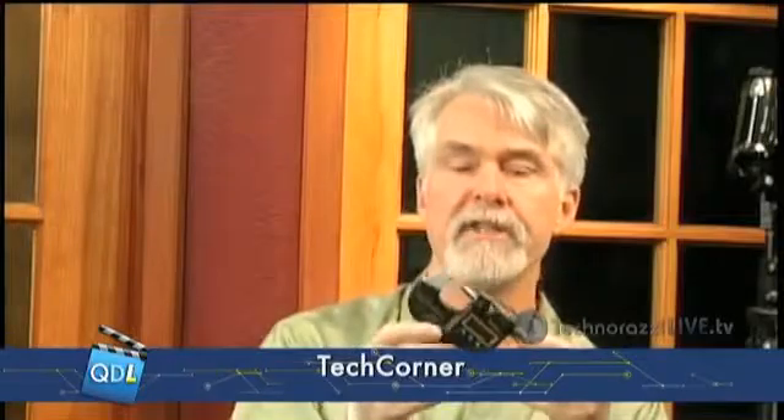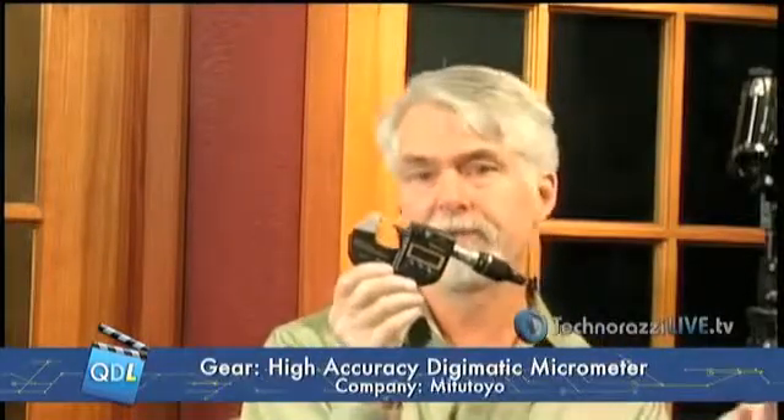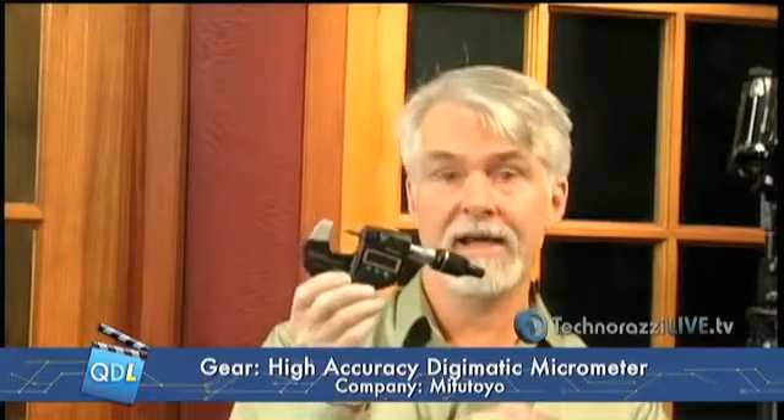We're fortunate enough to have one of Mitutoyo's brand new micrometers with us today, and Dirk is going to demo it for us. You're probably wondering why I'm putting these gloves on. If you remember our series of videos we did with Craig Howell at CPM Labs, when you're dealing with something like gauge blocks, you've got to make sure you don't get oil on them — they're precision instruments. So even in this setting, we really want to handle our gauge blocks with gloved hands. This particular micrometer, according to Mitutoyo, is the only 0.1 micron, 5 micro-inch handheld micrometer in the world — brand new from Mitutoyo, and we're one of the first ones to get one.